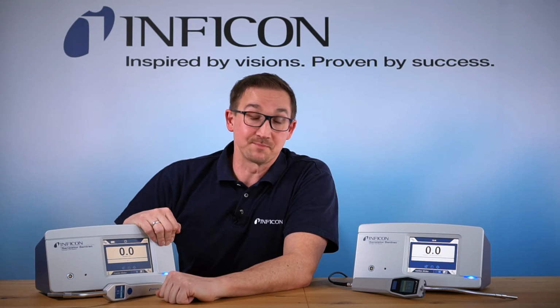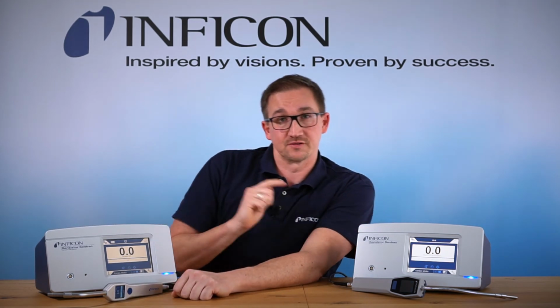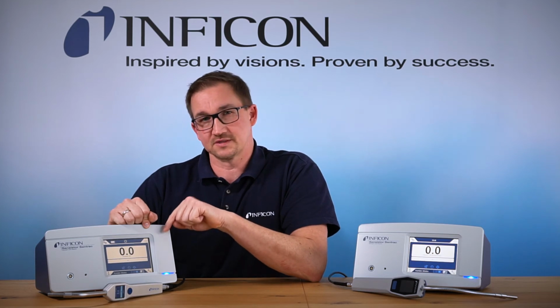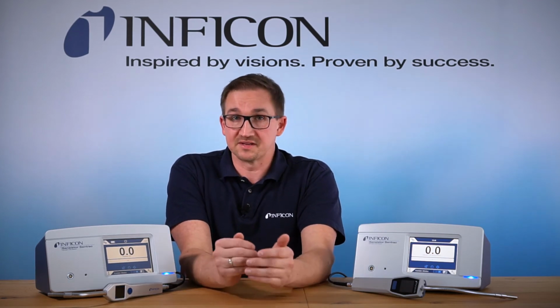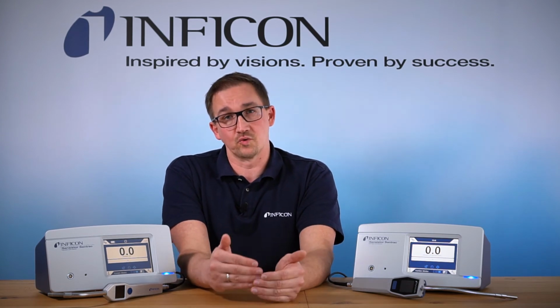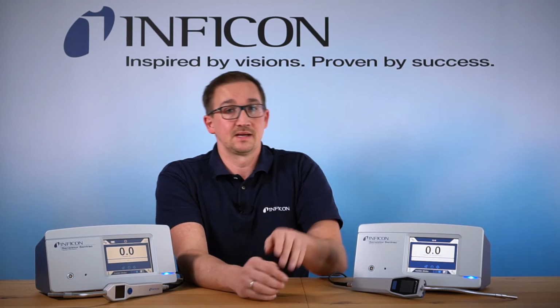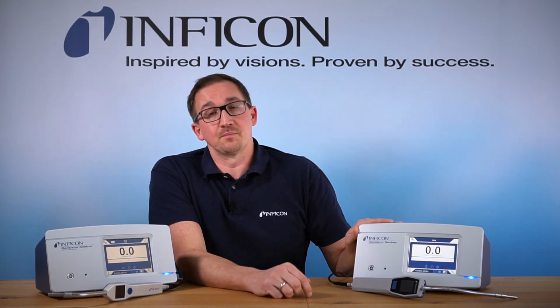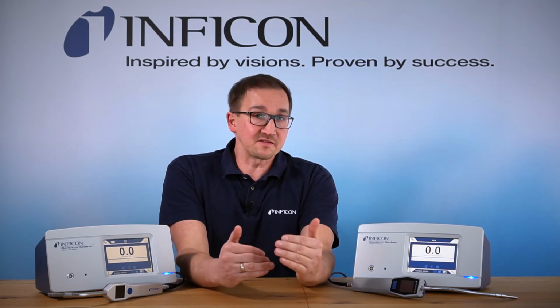With all the benefits offered by the new Strix edition, is there any reason to look at the standard version of Sensistor Sentrac? The very simple and clear answer is yes, because each of these two models is optimized for completely different applications. Manual leak testing is an operator-dependent test method. It works just as well as the individual operator who is doing the leak test. In general, this operator dependence becomes even bigger the smaller the leaks you need to find. The new Strix edition is designed to reduce this operator dependence to a minimum when finding smallest leaks, improving the process safety of the overall leak test.